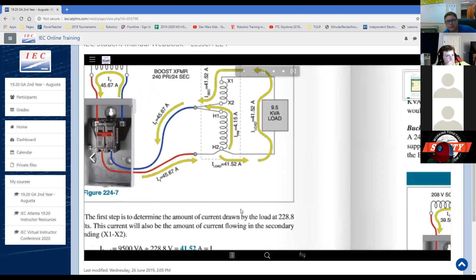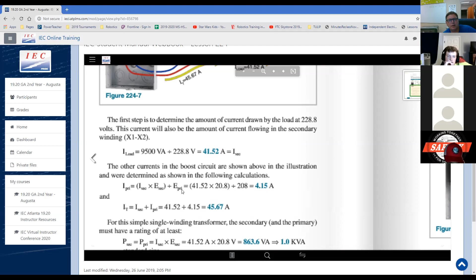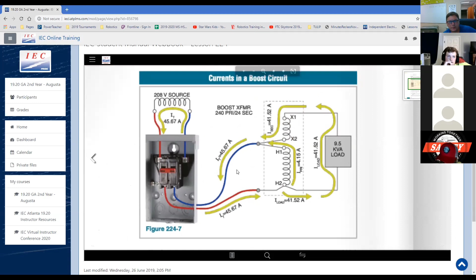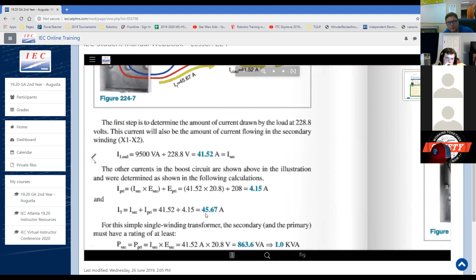When you take the 41.52, which is the secondary current, and multiply that by the voltage of the buck boost secondary, 20.8, then divide by our primary voltage, which was 208, we get 4.15 amps. Now we add those two together: 41.52, our amperage through the secondary, plus the buck boost gives us 45.67 amps.